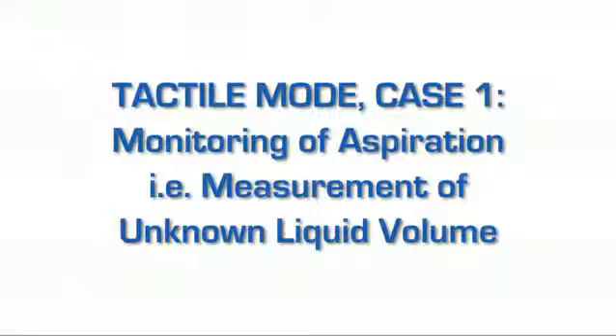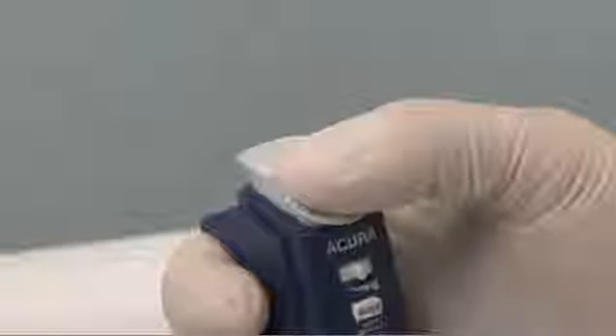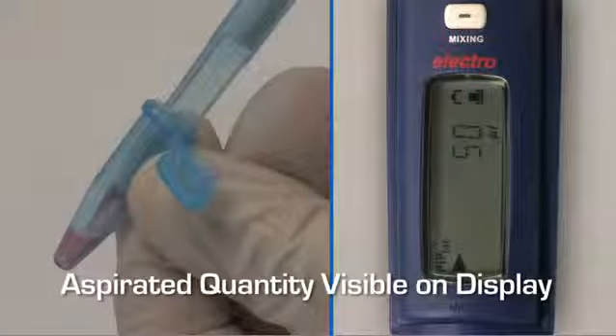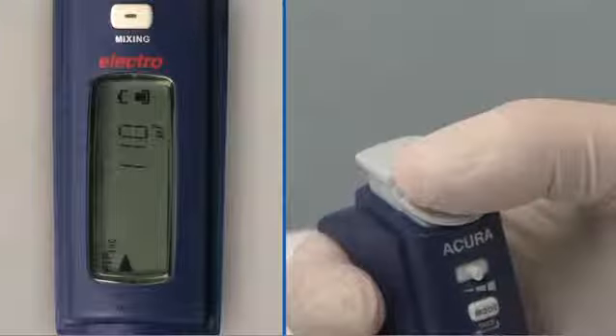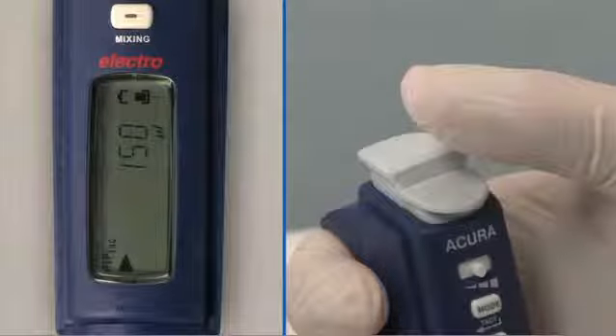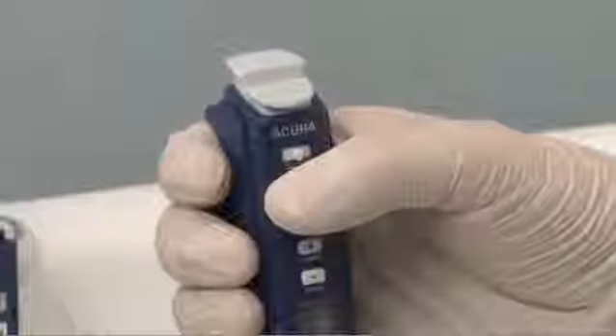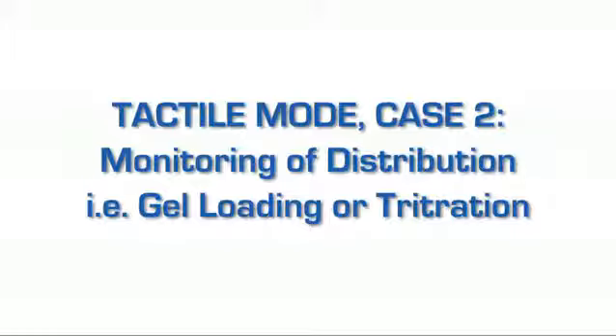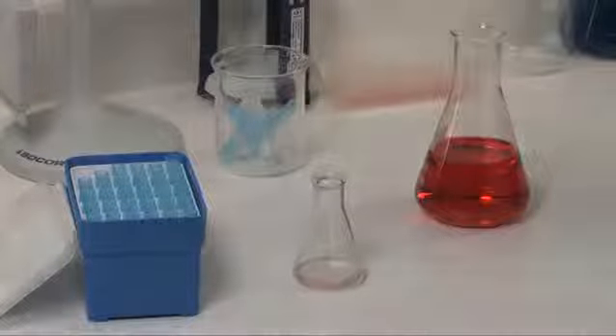Case 1. Monitoring of aspiration. Take the new tip and introduce it into the liquid. Very gently press the Start button until the first stop and let the liquid be aspirated very slowly. The display shows the aspirated volume. Any release of the Start button will stop the aspiration process. When aspiration is completed, press mode to enable distribution of the liquid. Case 2. Monitoring of distribution. Take the new tip and introduce it into the liquid.